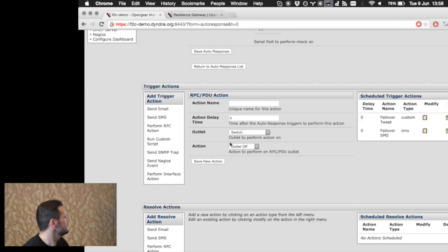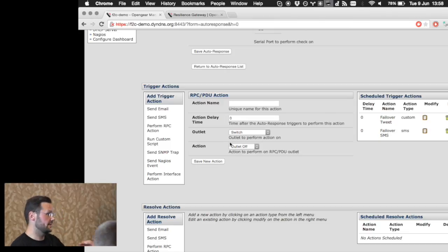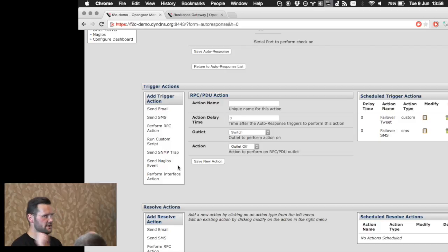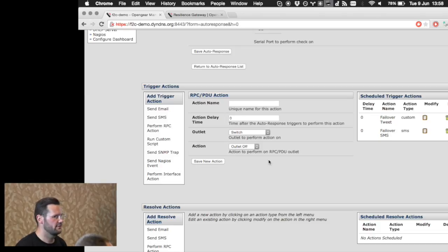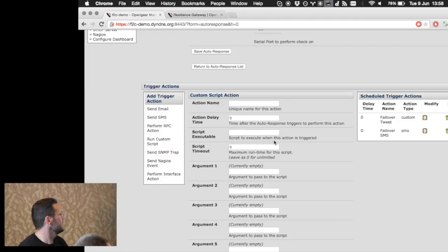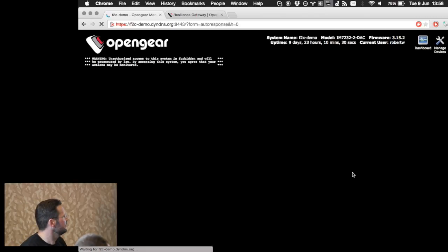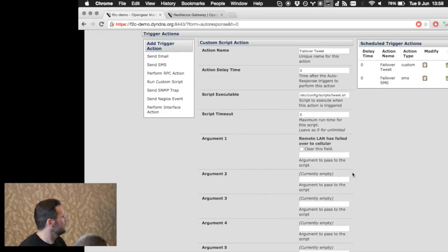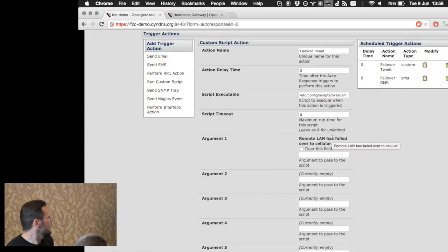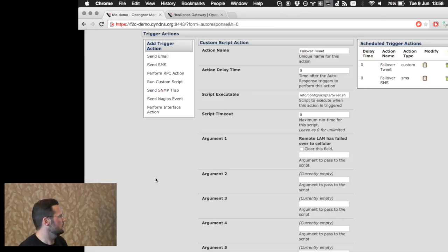You can also control power — automatically cycle an outlet. Another cool thing is you can have escalating actions: at minute zero you might send an SNMP trap to your NMS, at minute fifteen you might start paging people, and if the situation is still ongoing after half an hour you can just start bouncing equipment to try and recover. You can also plug in your own custom scripts — that's what the tweet action was.